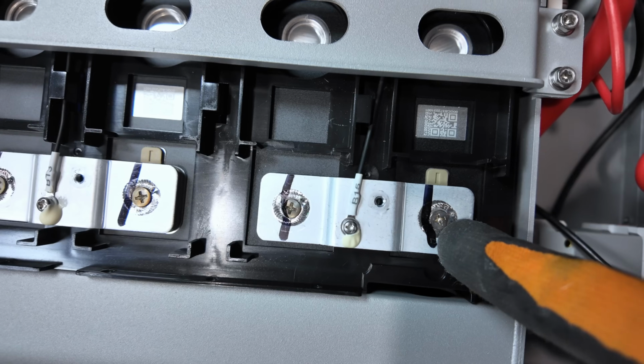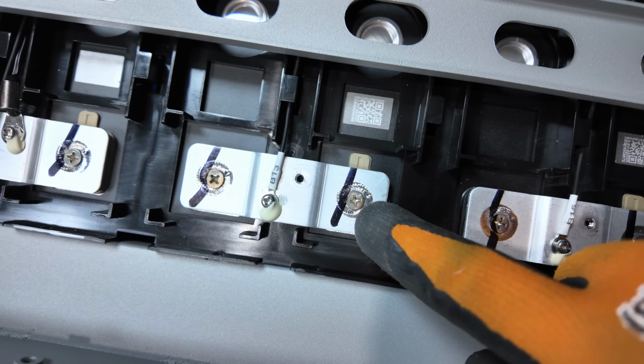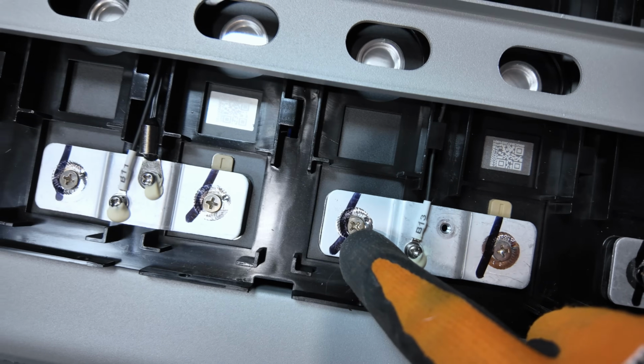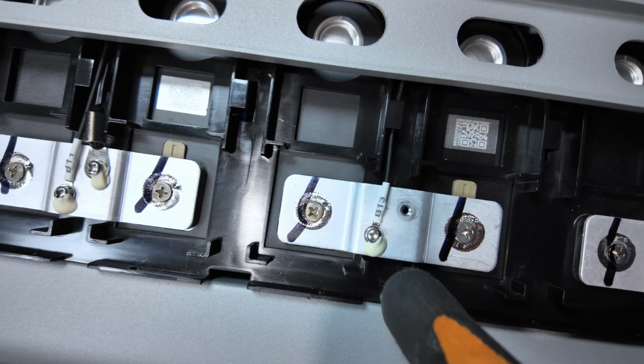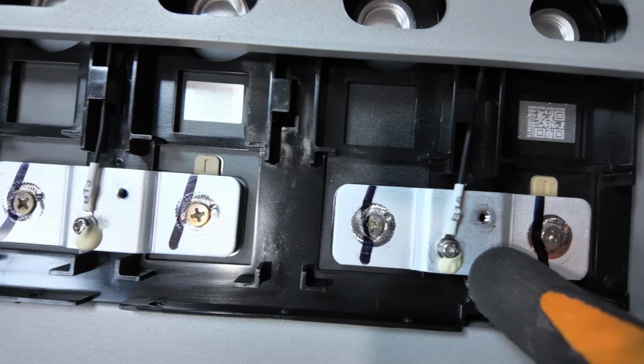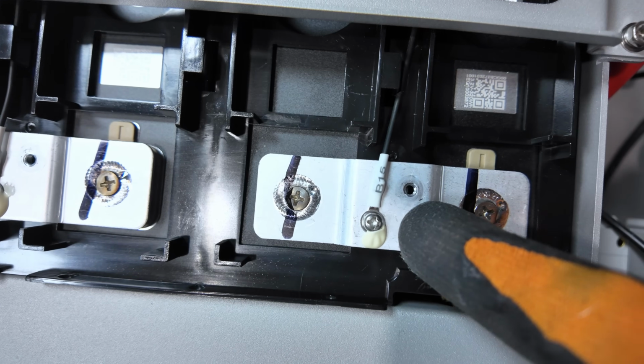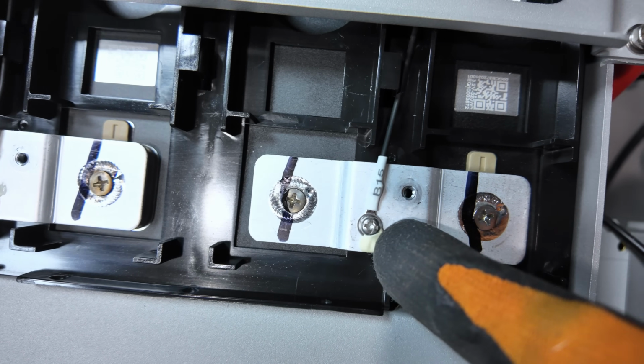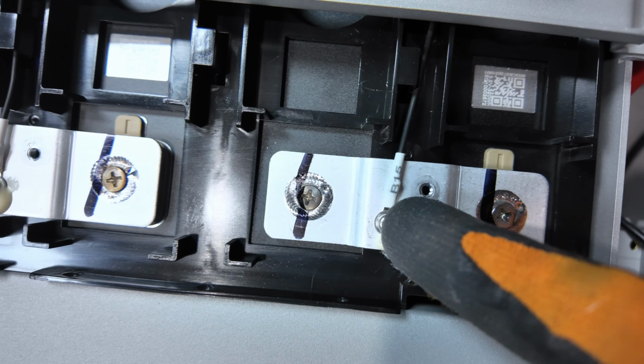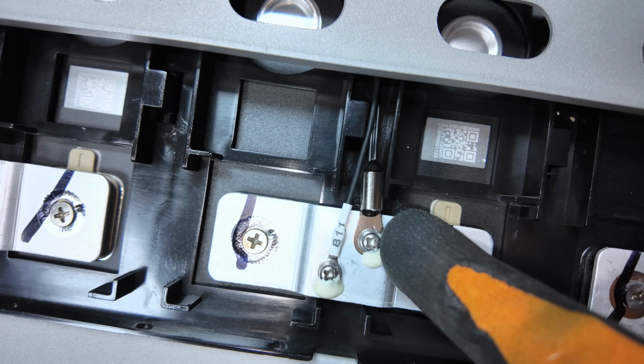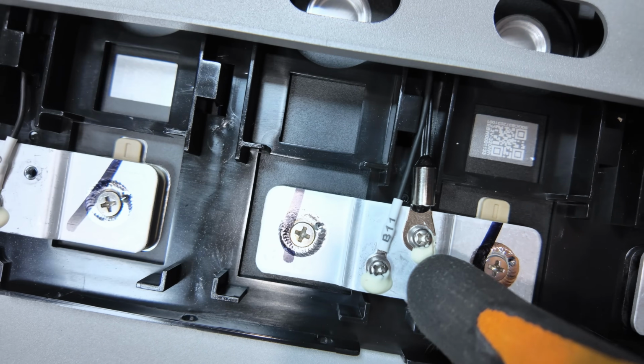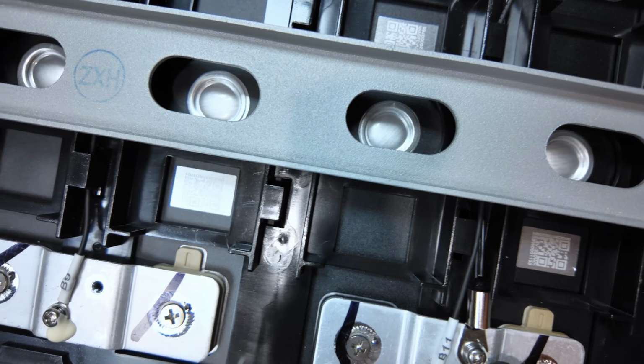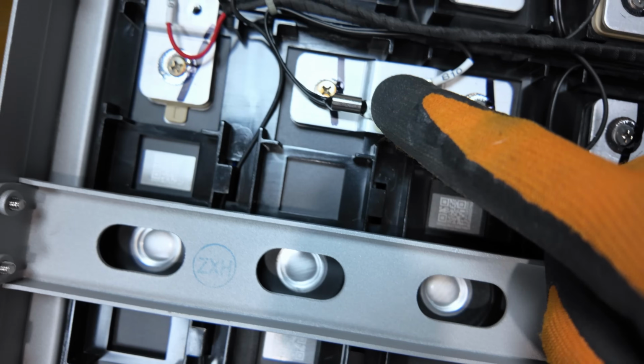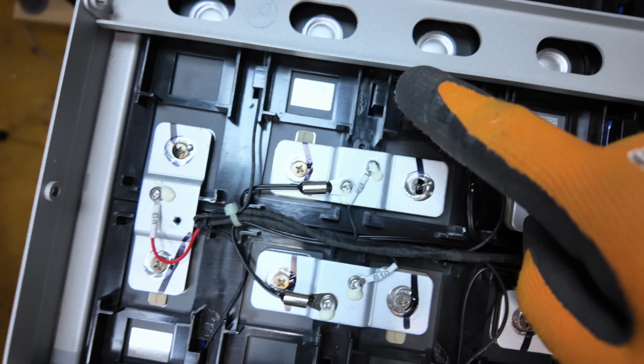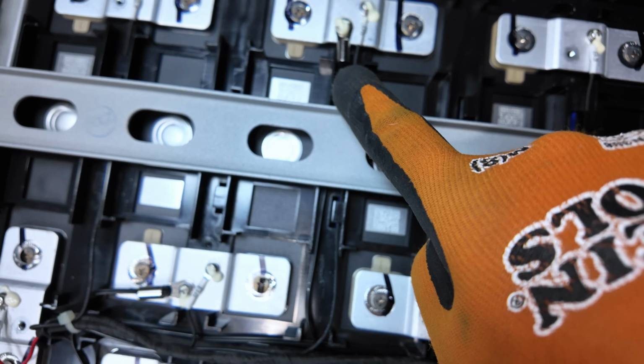We have marks on each connection point signifying it's been checked. We see our different balance leads, screwed directly down to the bus bar, with some silicone goop to keep them from moving. We have several temperature sensors placed on top of the bus bars, which I love to see, in different locations across the battery.